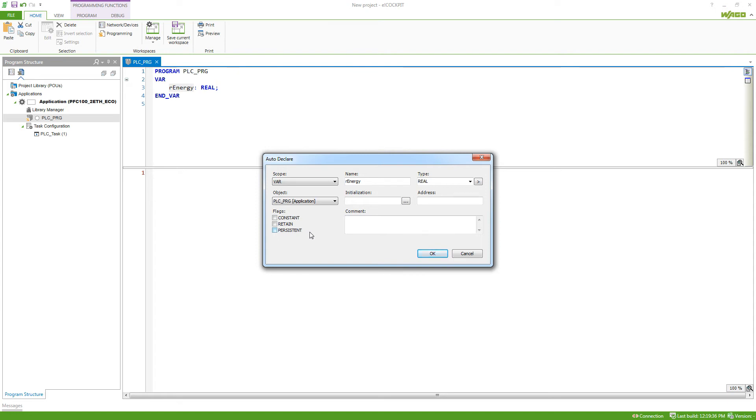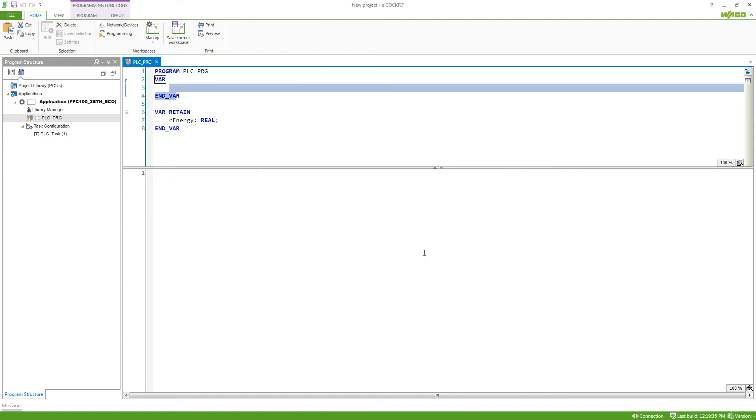So I will select retain here and hit OK. You can see now the variable is being moved to the var retain area, and so this variable won't be changed even if we perform a reboot of the controller.